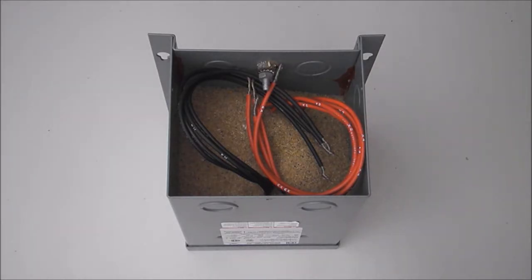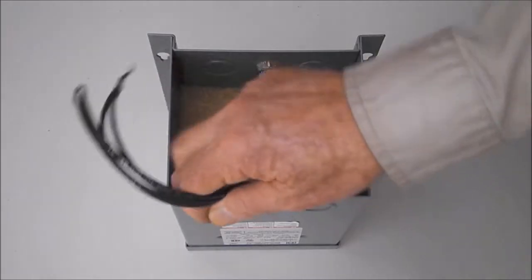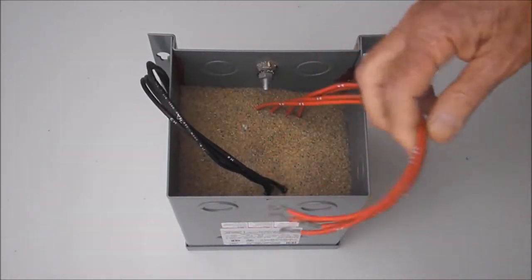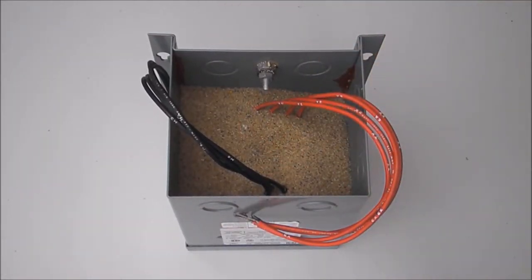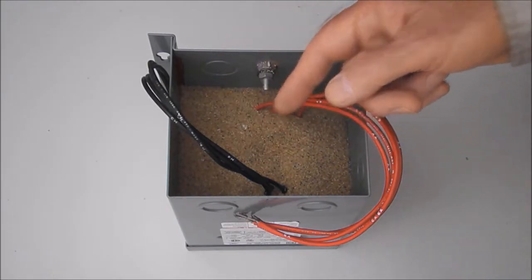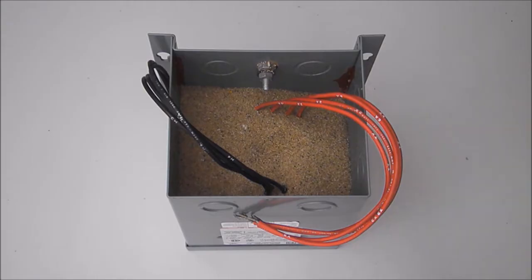All such transformers have four H connections and four X connections. On this particular transformer, the H wires are black and the X wires are red. This coloring is visually convenient, but is not always the case. Sometimes all wires are black, sometimes all are red, and so forth.